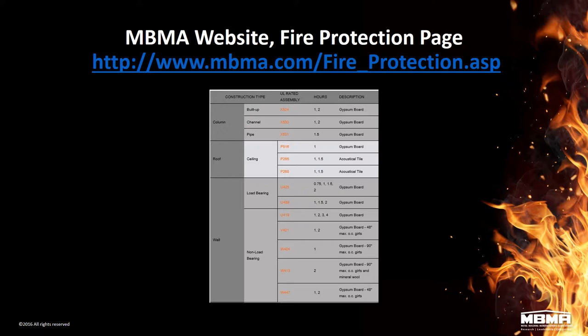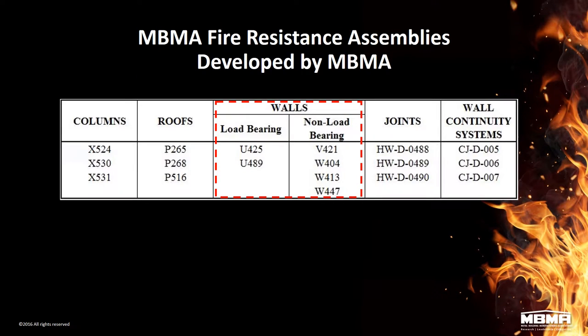Here's a summary highlighting the six UL assemblies that MBMA has sponsored over the years. The load bearing walls are U425 and U489. The non-load bearing walls — mainly exterior walls — are V421, W404, W413, and W447. As noted in part two regarding UL nomenclature, U, V, and W are the alphabetical prefixes for walls, and the 400 series indicates gypsum board protection. These are all consistent with that system.